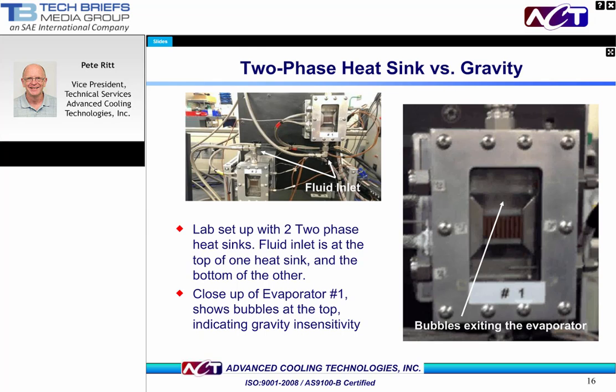Another question frequently asked is, are P2P systems sensitive to gravity? The answer is no in properly designed systems where inlet pressure is well controlled. Here we see a lab setup with 2 parallel evaporators with flow going in opposite directions. Both can be seen in the picture on the upper left. Here, evaporator number 1 has inlet flow coming in the bottom and coming out the top. Flow is going against gravity. Evaporator number 2 has flow coming in the top and coming out the bottom. This orientation is called gravity aided. As you can see, bubbles are exiting both evaporators, and both evaporators are at the same temperature.